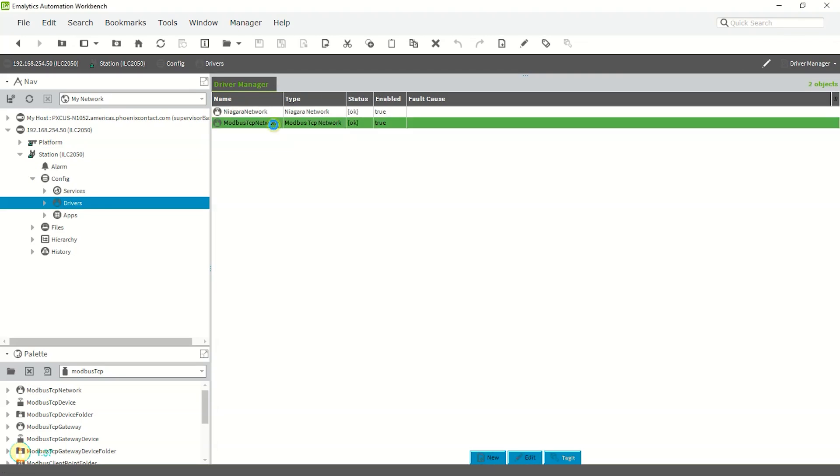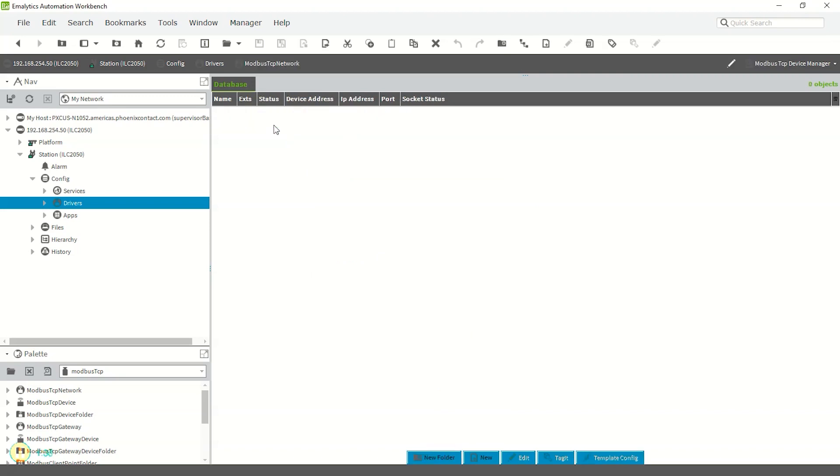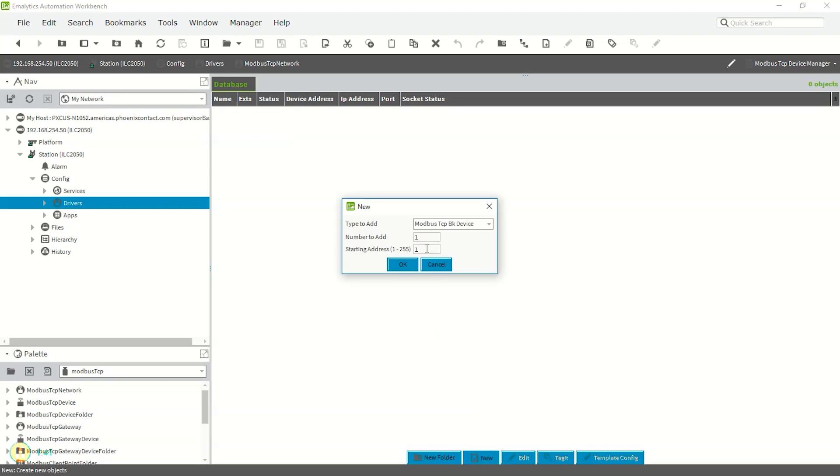Double-click the newly made Modbus TCP network driver to enter its database. This database is where Modbus devices are added to enable communication. Click the New button at the bottom and make sure Type to add is Modbus TCP BK device and starting address is 1, and hit OK.